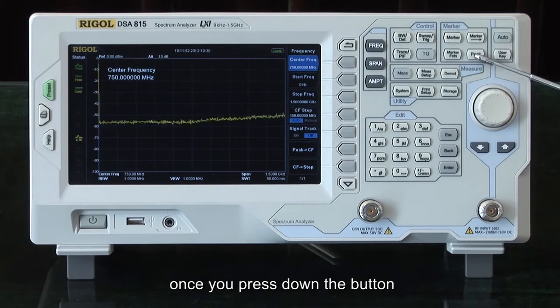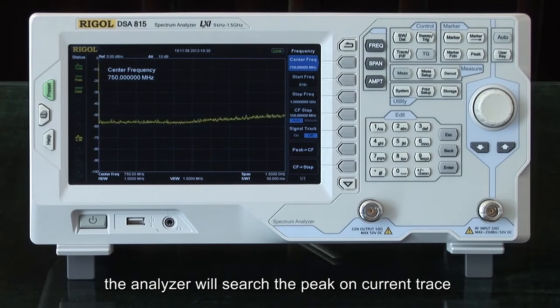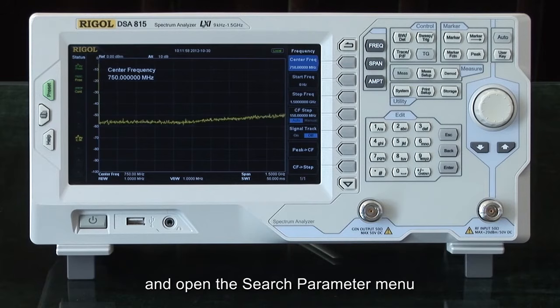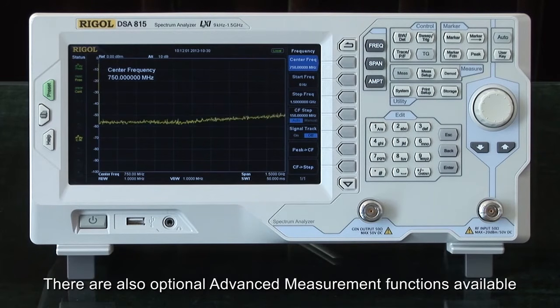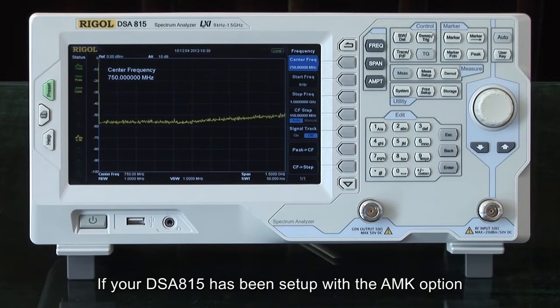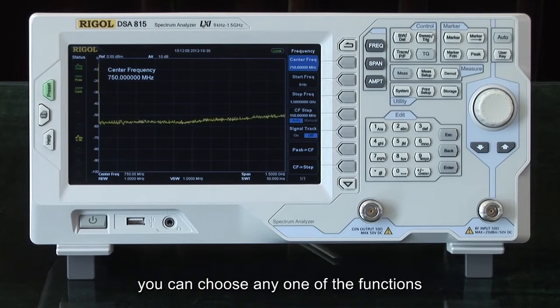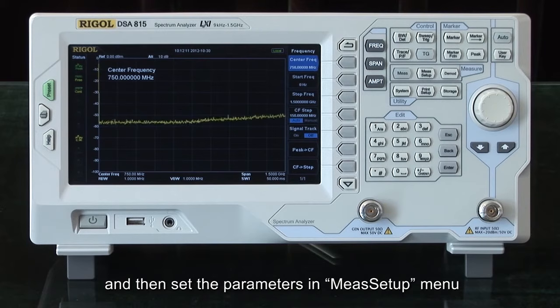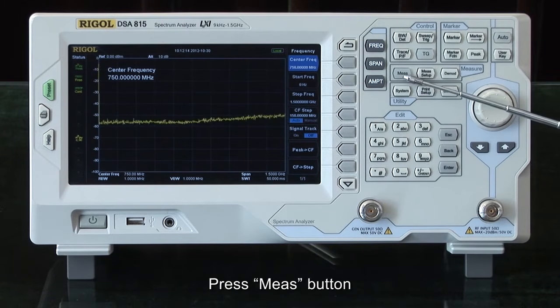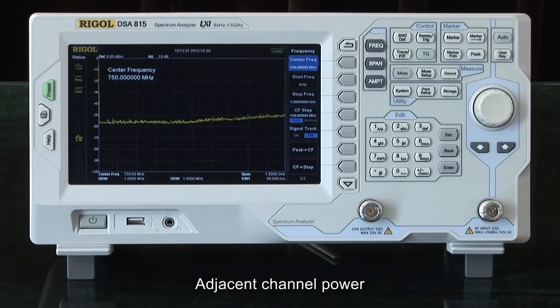For the peak function, once you press the down button, the analyzer will search the peak on the current trace and open the search parameter menu. There are also optional advanced measurement functions available. If your DSA815 has been set up with the AMK option, you can choose any of the functions and set the parameters in the Measure Setup menu. Press the Measure button, and we can see the advanced measurement functions VSWR, total power, adjacent channel power, occupied bandwidth, emission bandwidth, carrier to noise ratio, harmonic distortion, and TOI.